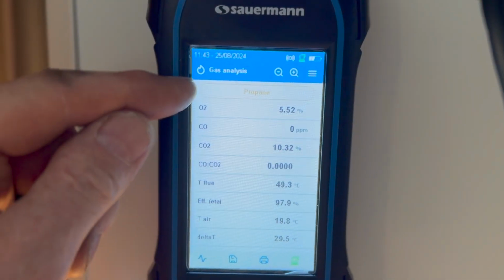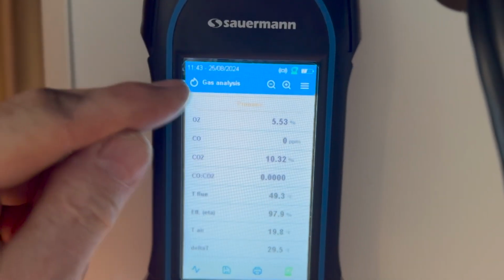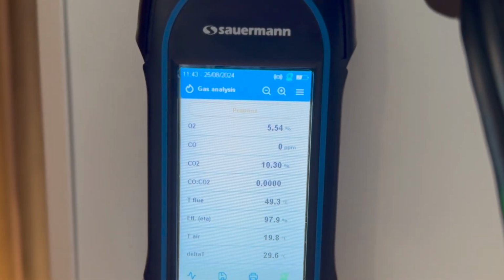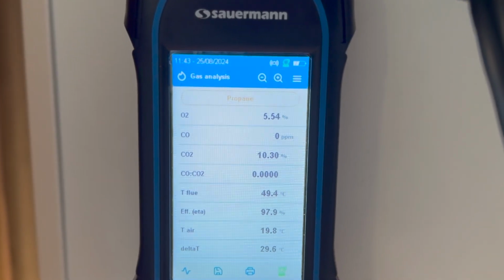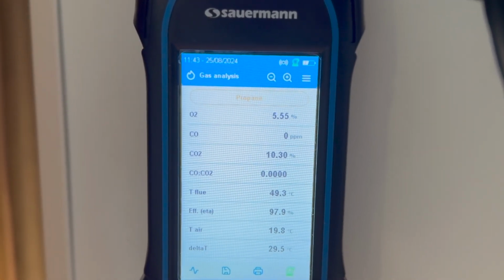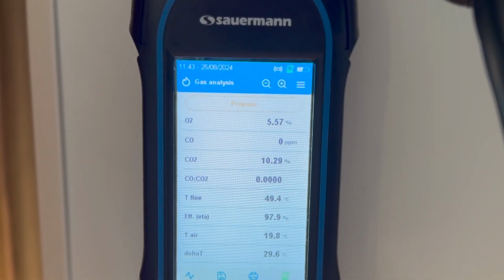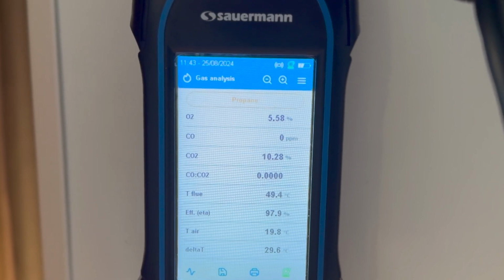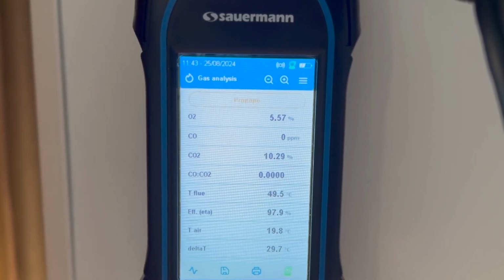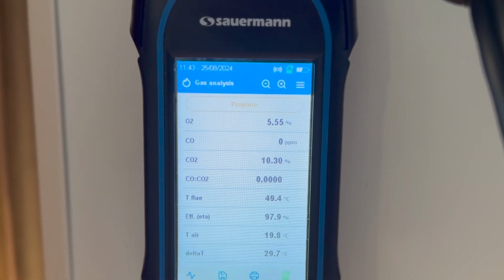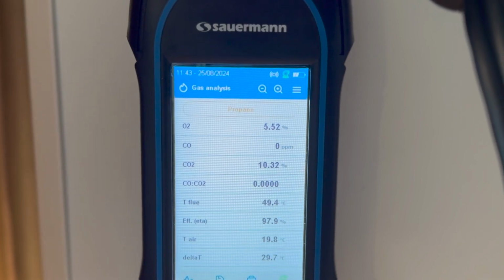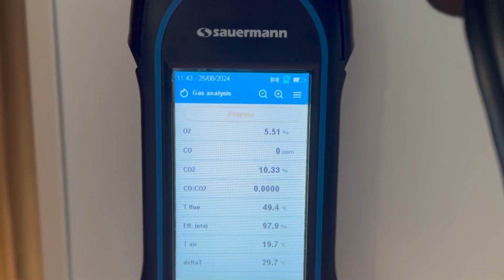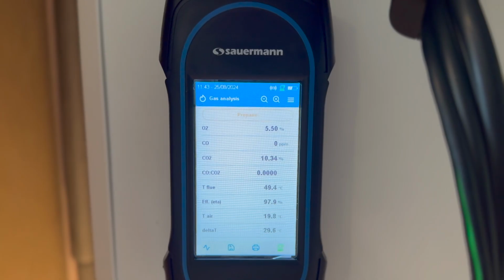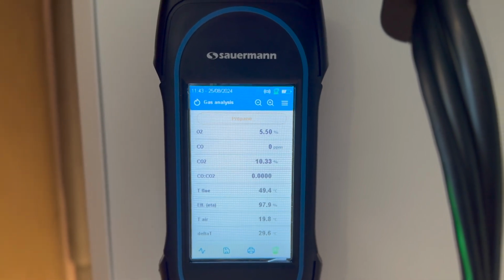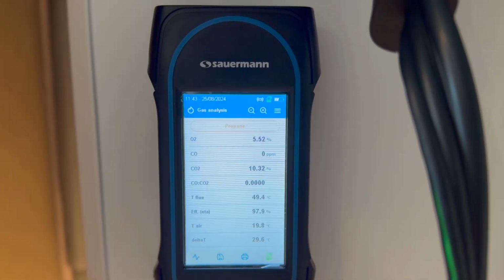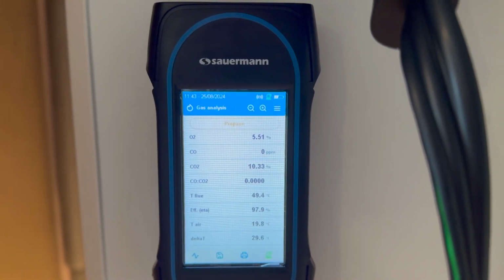Now you can see the analyzer is set in propane. It's dead easy to do that. You just press on where it says propane and you can pick which gas you want. Then you can see we've got an O2 of 5.5. We have no CO whatsoever. We have a CO2 of 10.3 and we have no ratio. So that's looking good because the range for this is 9.5 to 10.5.